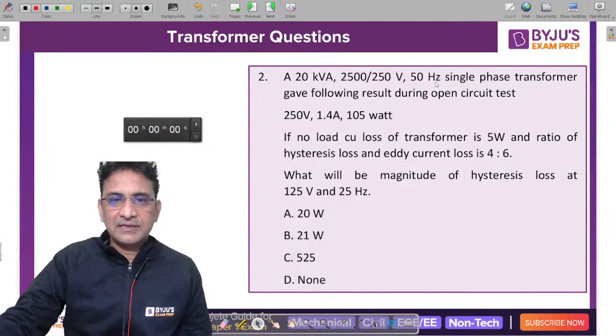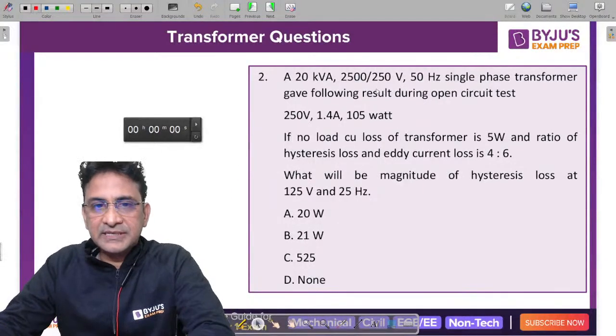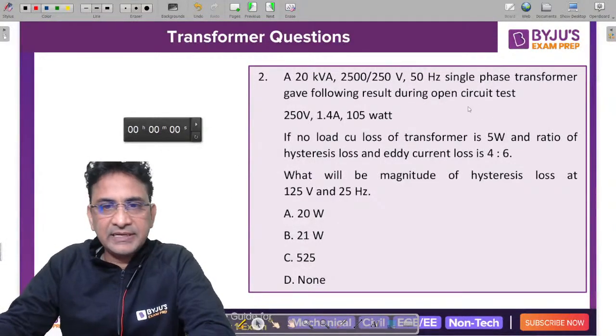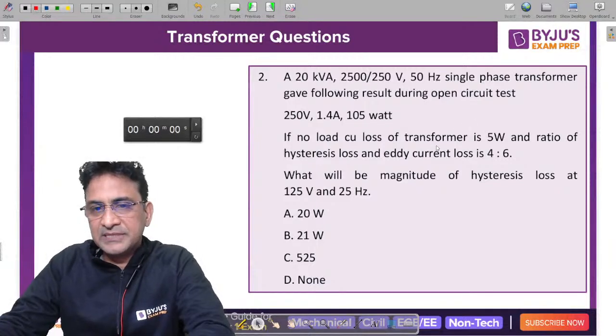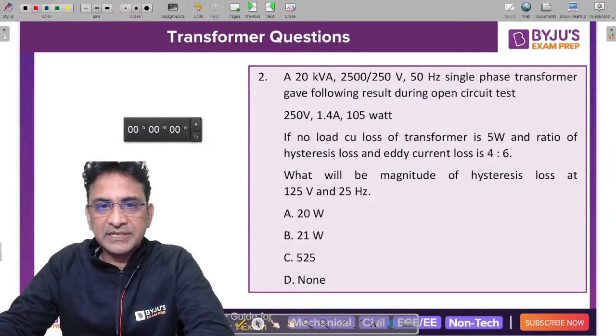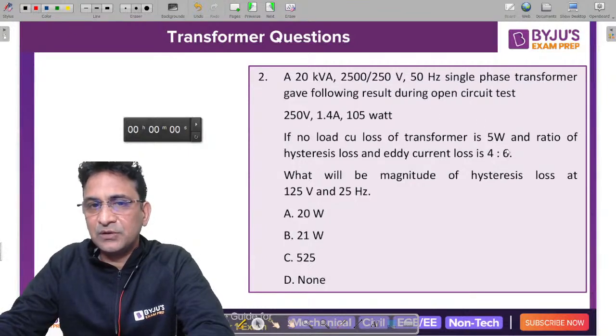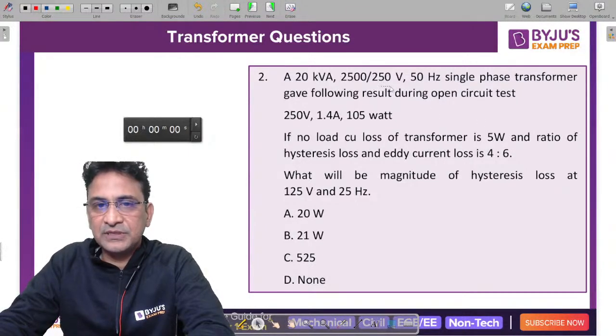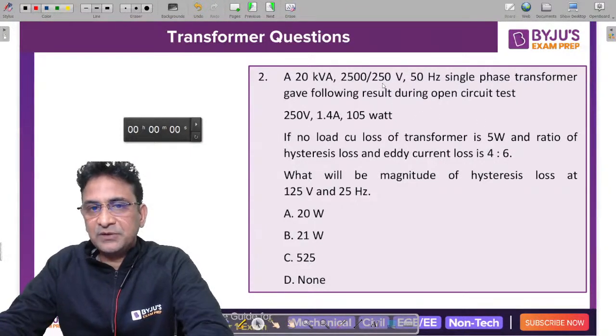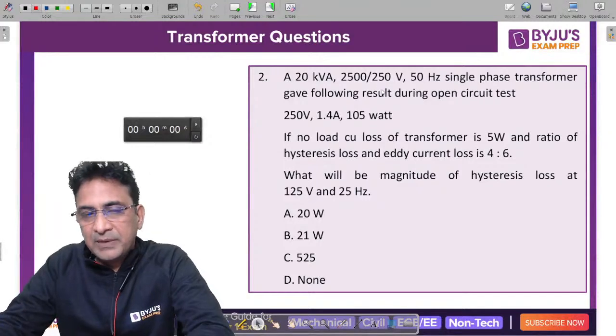Okay. See, the open circuit test is mainly conducted on the low voltage side. If it is not mentioned on which side we are conducting the open circuit test, then you imagine that we are going to conduct the open circuit test only on the low voltage side. That means the 250 volt side. So when we are doing the open circuit test, we apply the voltage.